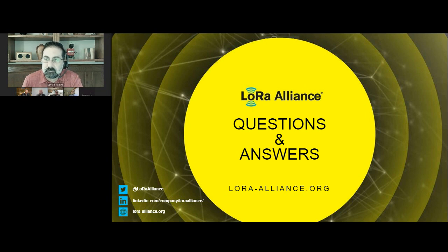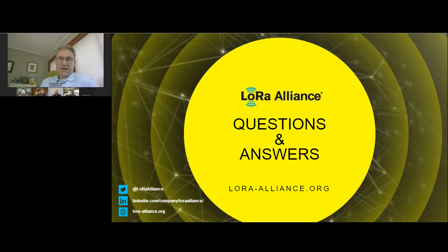Dan, if I can also add to that, Byron: the question was what protocols are recommended for the back end. In a sense, that depends on your back end, doesn't it? As David just said, maybe a SCADA system uses Modbus, a production piece of equipment uses OPC UA, and building management systems actually use all of these protocols, BACnet and others too. So it's really the back end that dictates the protocol that gets used.